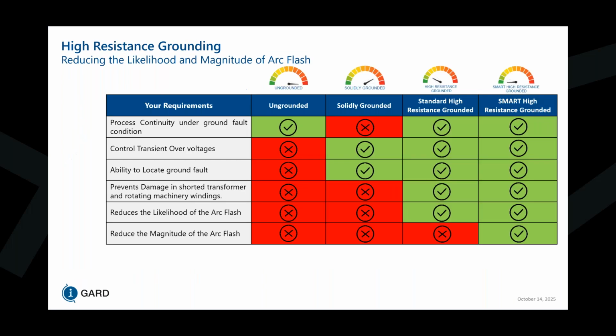So with the advanced high resistance grounding offering, we can also provide reduction in the magnitude of an arc flash with the utilization of an arc flash sensor. And this will provide a more secure system than just the standard high resistance grounding offering.